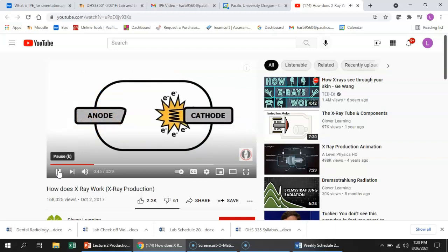Electrons are produced in the X-ray tube at the cathode filament. The specific process is called thermionic emission, which is the release of electrons, ions, in response to heat. And so it makes sense that it's called thermionic emission. A current running through the filament causes it to become extremely hot. So hot that electrons are actually dissociated from the metal and form an electron cloud around the filament. This is kind of like the filament in an incandescent light bulb. A current running through the light filament creates heat, which creates the light. In an X-ray tube, the filament gets so hot, it actually creates free electrons.